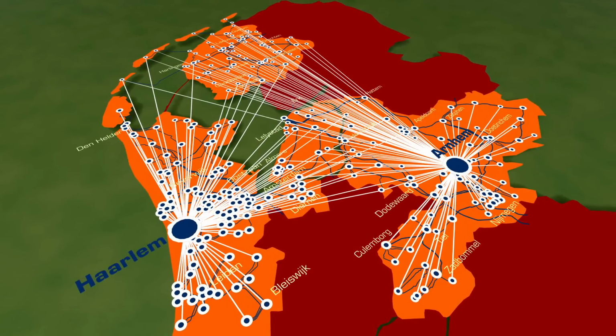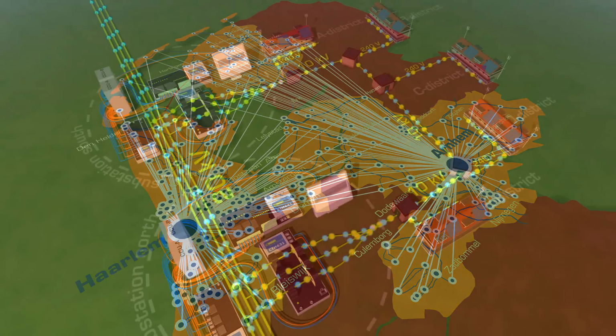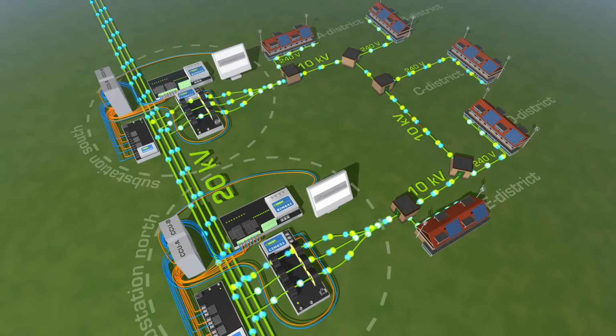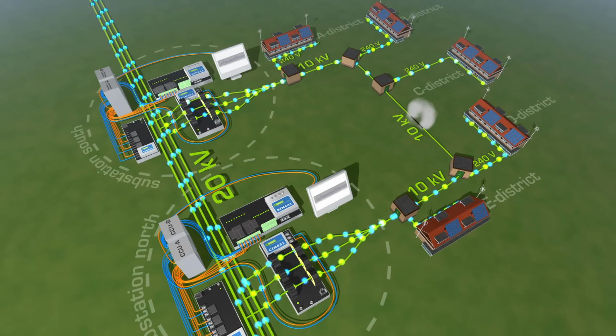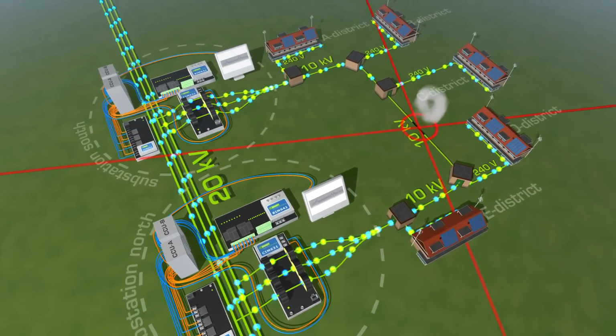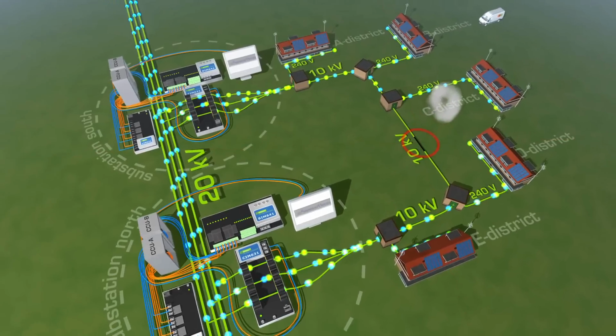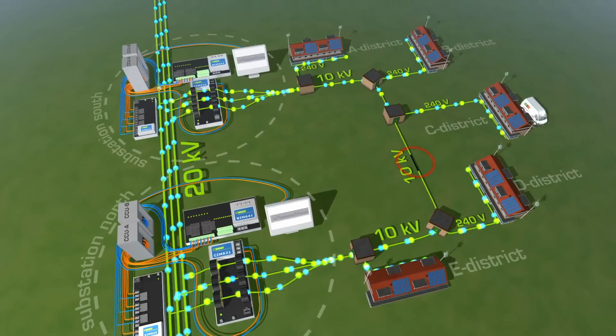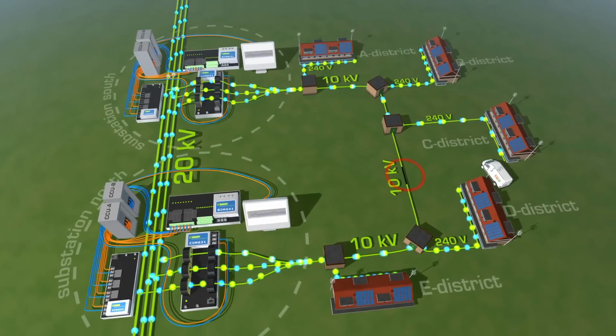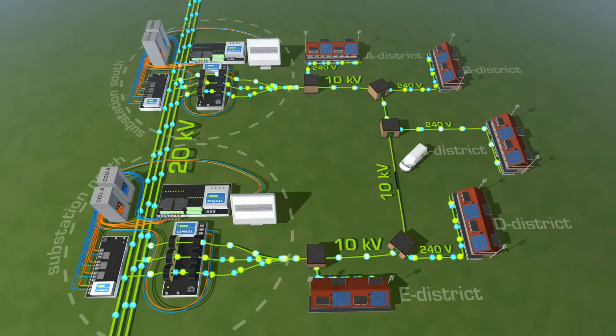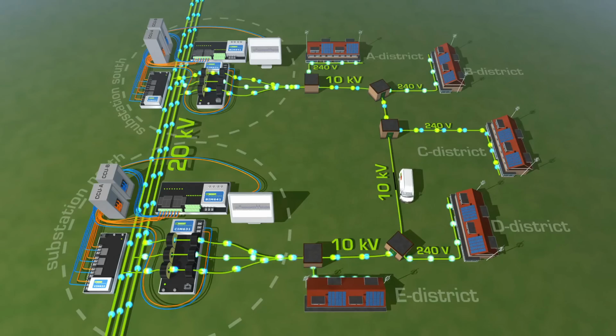Another advantage is the automatic detection of a fault location. In the event of a power failure, the new system fully automatically localizes the fault in the cable network, within a minute down to the exact location. The engineer has no need to search for a location, he simply drives directly to the correct location. For that matter, a part of the present maintenance will no longer be necessary.